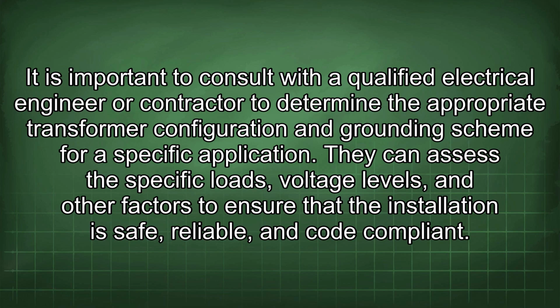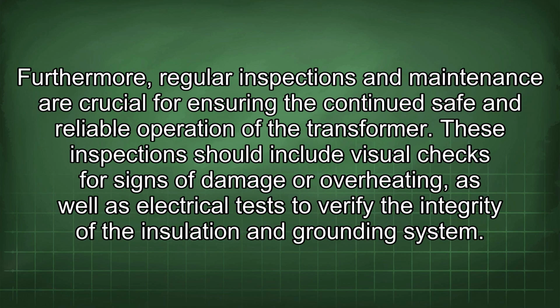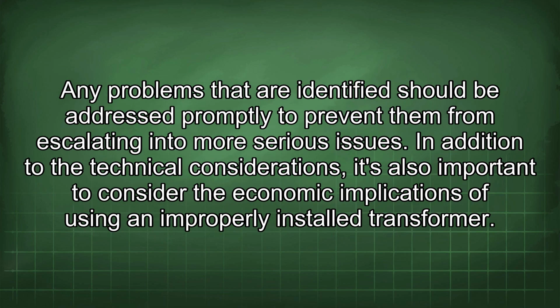They can assess the specific loads, voltage levels, and other factors to ensure that the installation is safe, reliable, and code compliant. Furthermore, regular inspections and maintenance are crucial for ensuring the continued safe and reliable operation of the transformer. These inspections should include visual checks for signs of damage or overheating, as well as electrical tests to verify the integrity of the insulation and grounding system. Any problems that are identified should be addressed promptly to prevent them from escalating into more serious issues.